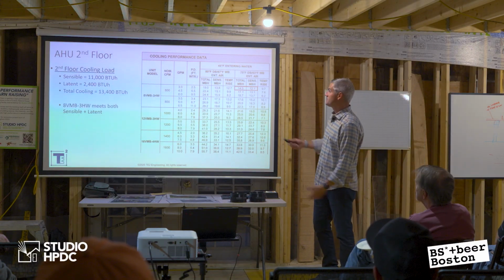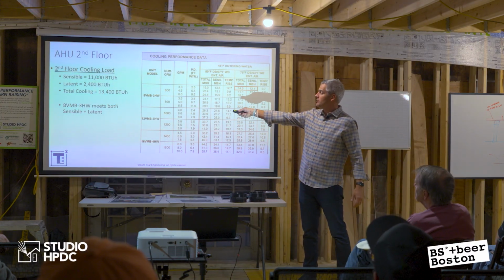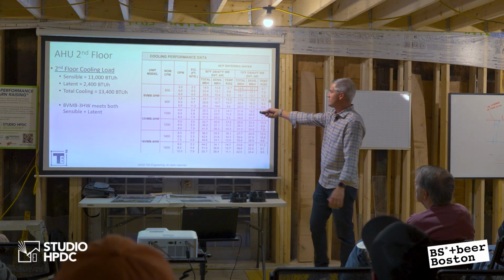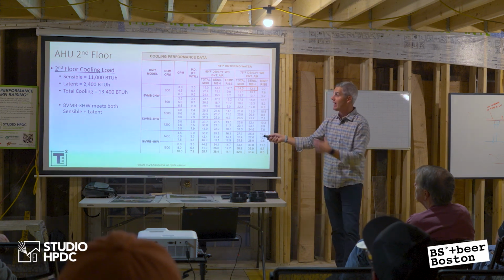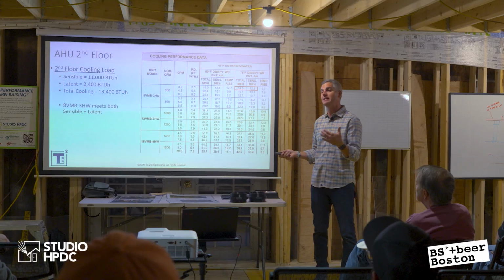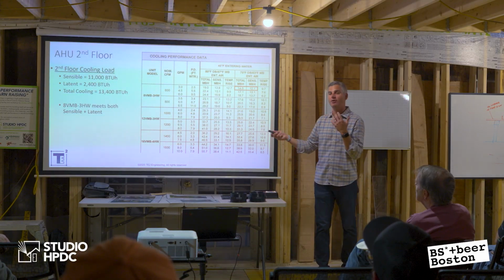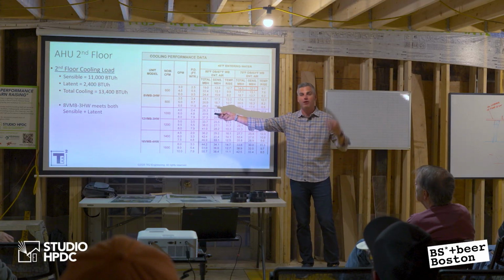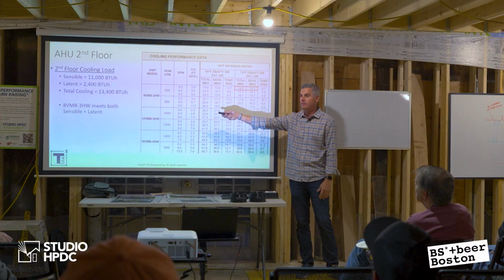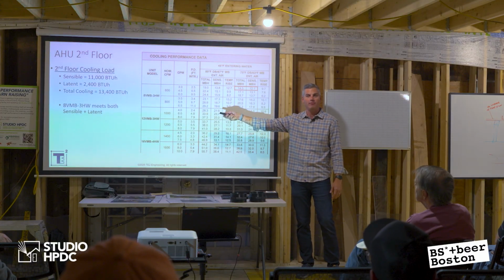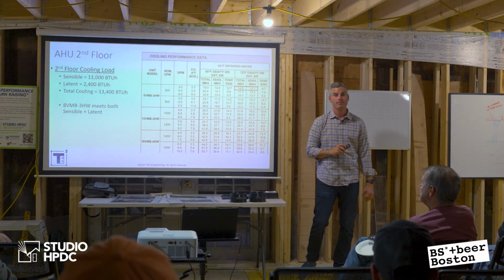Second floor, here's my sensible load, here's my latent load, total cooling. The smallest unit easily does it, and I don't have supplemental dehumidification up there. I don't need it. I'd meet the load up there because I don't have as many people. My latent load is much more manageable. I have 3 or 4 people up there, so not a lot of ventilation load, not a lot of latent load.